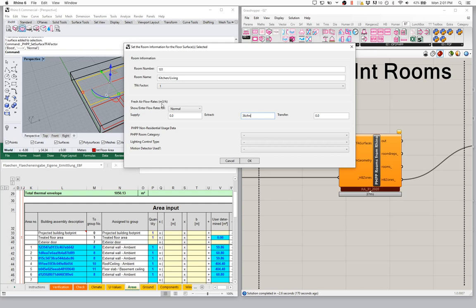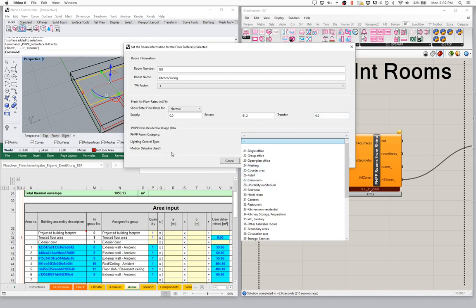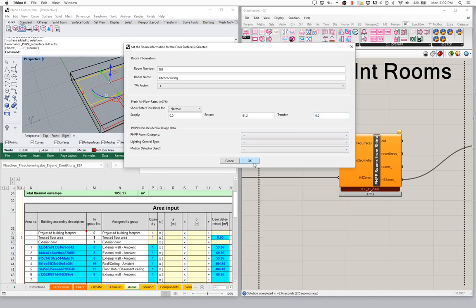Notice that the fresh air flow rates are in cubic meters per hour — the whole tool is built in metric. But if you like, you can pass in information in IP units. I can just say CFM and it'll convert that over to cubic meters per hour. So maybe I've got 36 CFM or 60 cubic meters per hour of continuous extract at normal fan speed from my kitchen or living zone, right through the ERV or HRV. So we'll say OK.